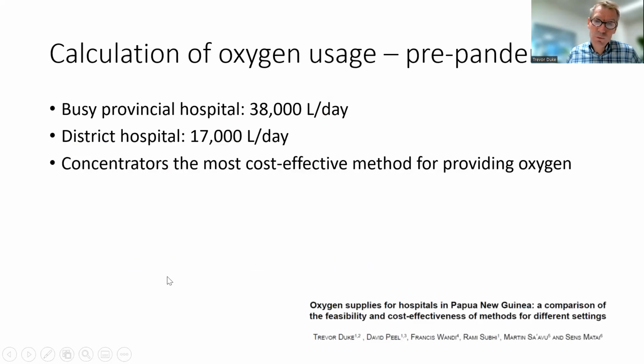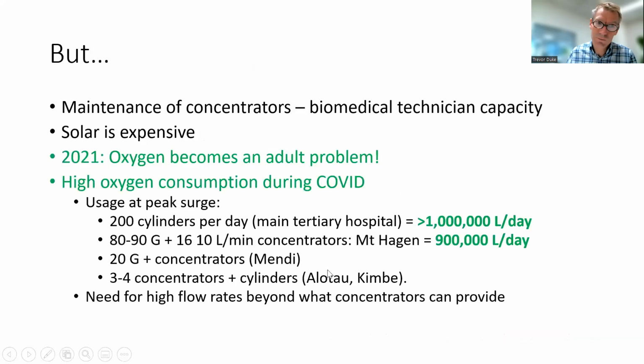Now, before the pandemic, back in about 2012, I calculated that the average busy provincial hospital used 38,000 litres of oxygen per day. And a district hospital, like I showed you before, Pomio and other places, requires about 17,000 litres of oxygen per day. This was calculated based on many studies measuring oxygen use by cylinders or concentrators in examples of these hospitals. And we concluded that concentrators were the most effective method of providing oxygen.